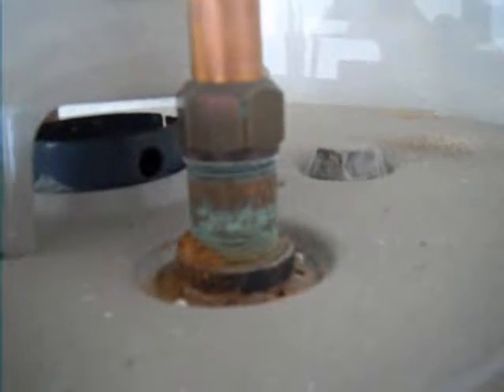Now what that indicates — and we've got it on both sides — is that there is deterioration in the condition of the water heater, and that's been occurring since it was installed because the water here is very acidic, and as a result it starts to corrode the system.